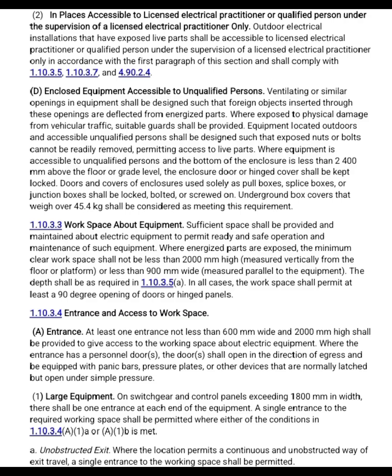This indicates that only licensed or qualified persons may access live parts. It is only accessible to licensed electrical practitioners or qualified persons under their supervision. This prevents untrained people from touching dangerous live parts. Equipment must be safe for unqualified persons. Any openings in electrical enclosures must block foreign objects from touching energized parts. If equipment is outdoors and can be hit by vehicles, a guard must be installed.